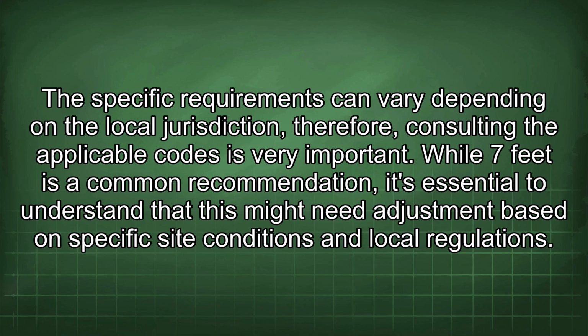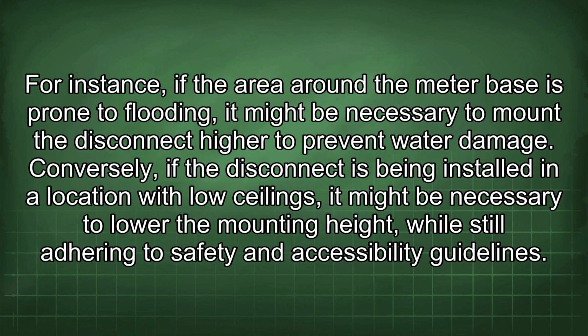While 7 feet is a common recommendation, it's essential to understand that this might need adjustment based on specific site conditions and local regulations. For instance, if the area around the meter base is prone to flooding, it might be necessary to mount the disconnect higher to prevent water damage. Conversely, if the disconnect is being installed in a location with low ceilings, it might be necessary to lower the mounting height while still adhering to safety and accessibility guidelines.